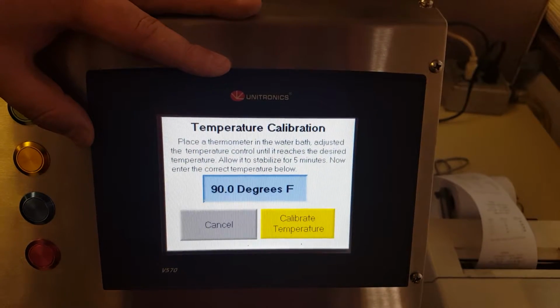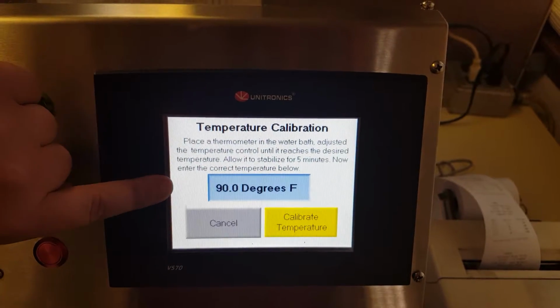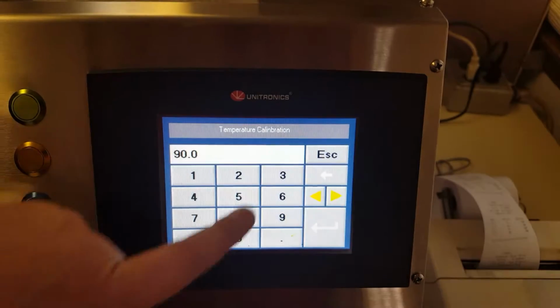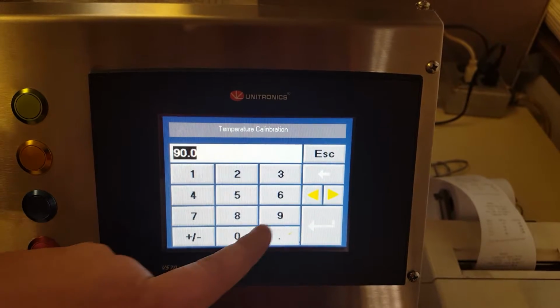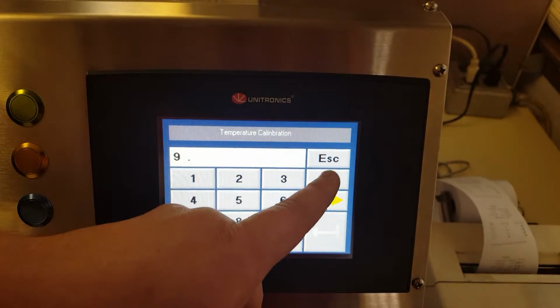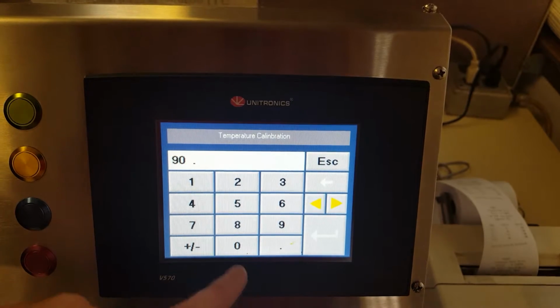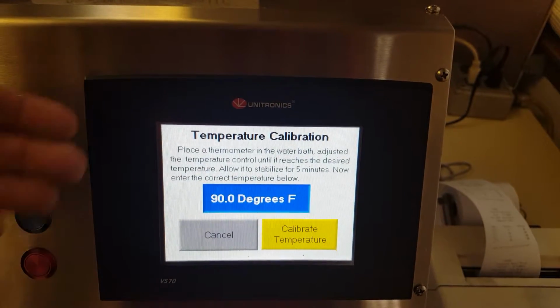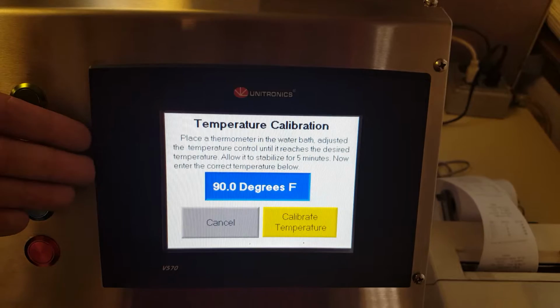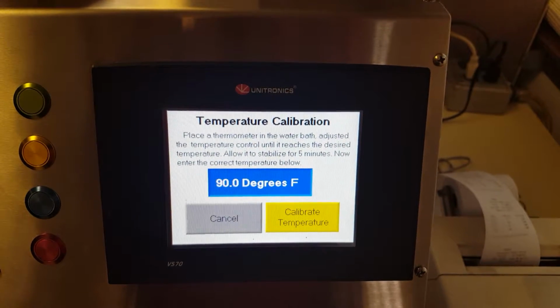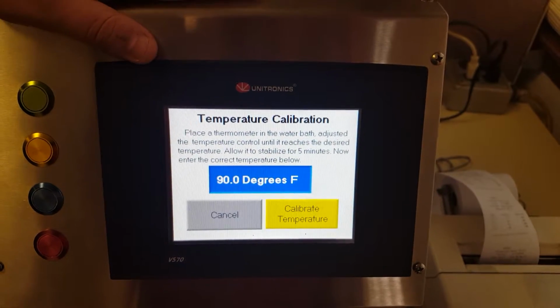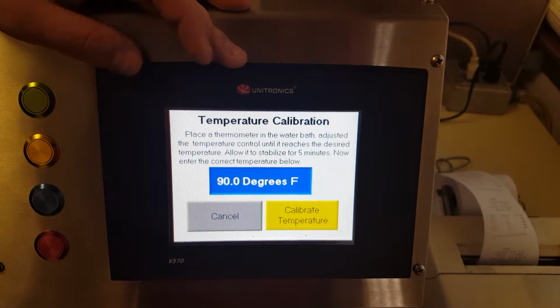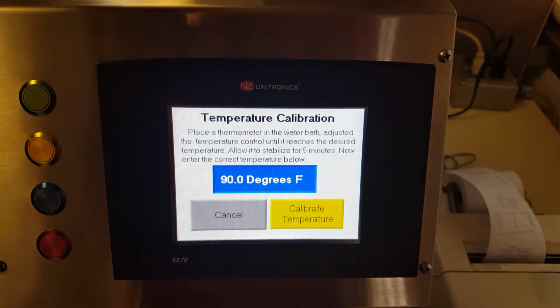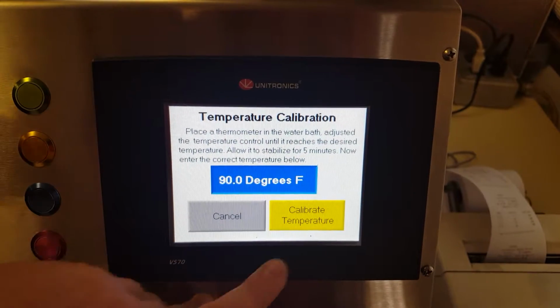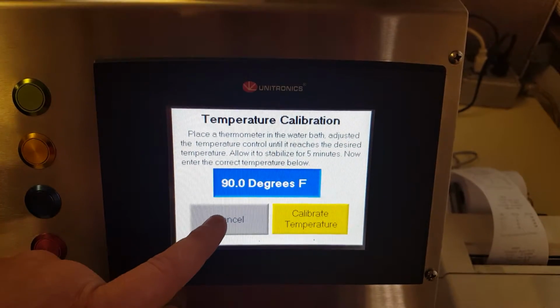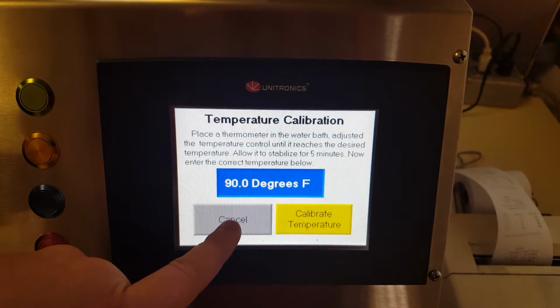Because this is for demonstration purposes, I'll simply explain that you can touch this setting here, and you can change this to whatever you want our screen to read. Of course, we want it to read 90 degrees, and that will display in Fahrenheit. Basically, we're telling the PLC, telling the machine, that the temperature coming in from our temperature probe and our external water bath is 90 degrees, and that's the number that will be displayed on both the screen and the printer printout. I'm not going to go through the entire calibration, just for demonstration purposes.